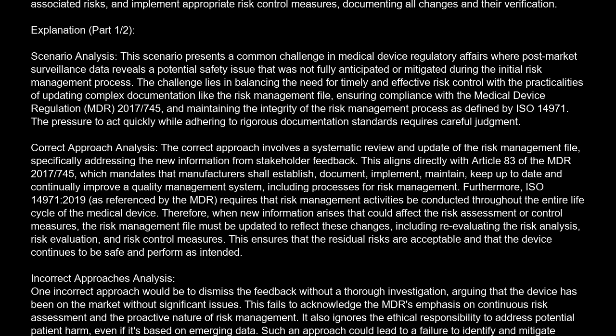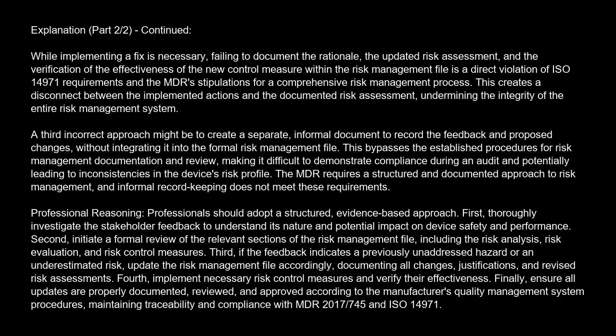Another incorrect approach would be to implement a corrective action without updating the risk management file. While implementing a fix is necessary, failing to document the rationale, the updated risk assessment, and the verification of the effectiveness of the new control measure within the risk management file is a direct violation of ISO 14971 requirements and the MDR's stipulations for a comprehensive risk management process. This creates a disconnect between the implemented actions and the documented risk assessment, undermining the integrity of the entire risk management system.